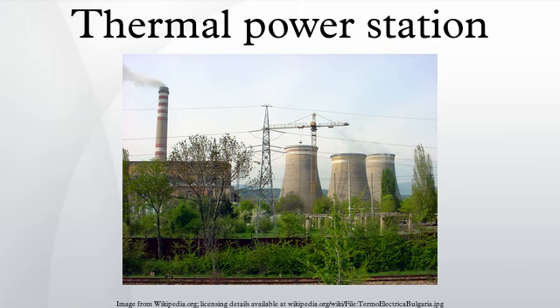In the steam drum, the water is returned to the downcomers and the steam is passed through a series of steam separators and dryers that remove water droplets from the steam. The dry steam then flows into the superheater coils. The boiler furnace auxiliary equipment includes coal feed nozzles and igniter guns, soot blowers, water lancing and observation ports for observation of the furnace interior. Furnace explosions due to any accumulation of combustible gases after a trip out are avoided by flushing out such gases from the combustion zone before igniting the coal. The steam drum has air vents and drains needed for initial startup.